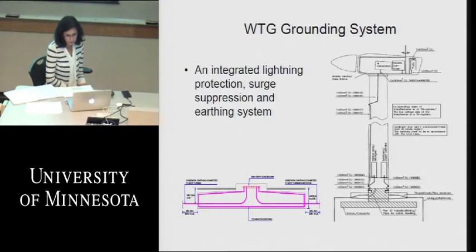The design on the left is a newer design that started around 2007, where we used the rebar within the foundation itself to form a UFER ground, named after a guy named Ufer during World War II who built ground systems for buildings out in the desert when the military was building a lot of construction in the desert during World War II with no water table to access. And so he used the steel within the foundation. And so we do that also. We run a copper conductor within the foundation before we pour the concrete and set the concrete. So with this copper, we connect it with the proper UL-listed grounding connectors to that rebar, and that creates the foundation as an electrode.